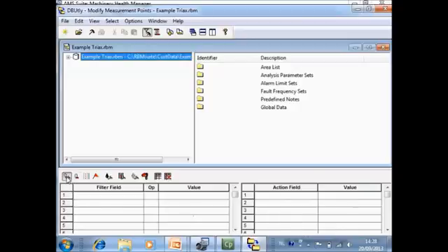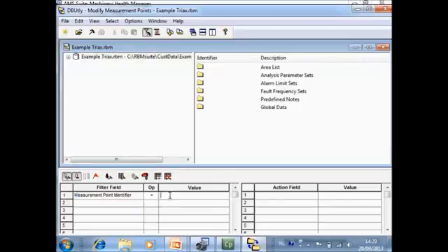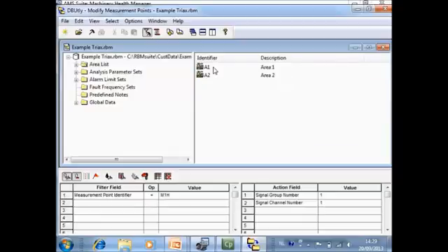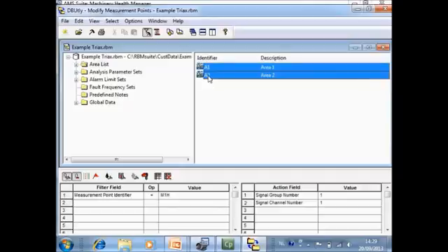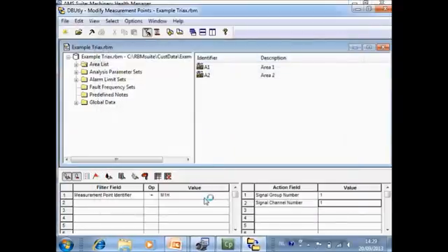Make sure the first two icons are activated. As a filter, use measurement point identifier equal to 'Motor 1 Horizontal'. Set the action to change the signal group number to one and the signal channel number to one. At the top, specify which part of the database you want to modify. Click the hammer and all measurement points called 'Motor 1 Horizontal' are now changed.